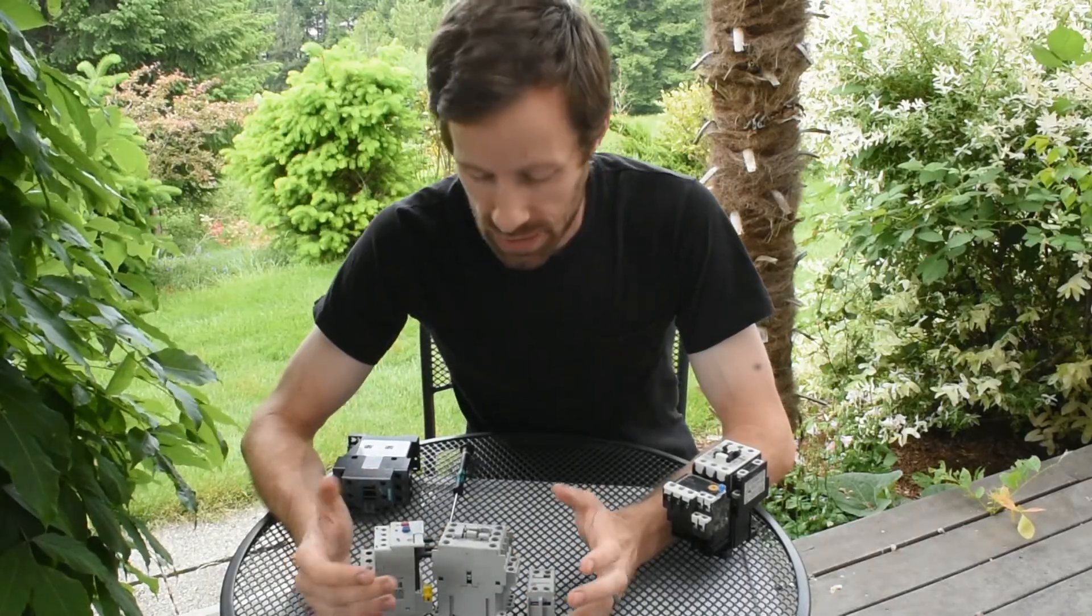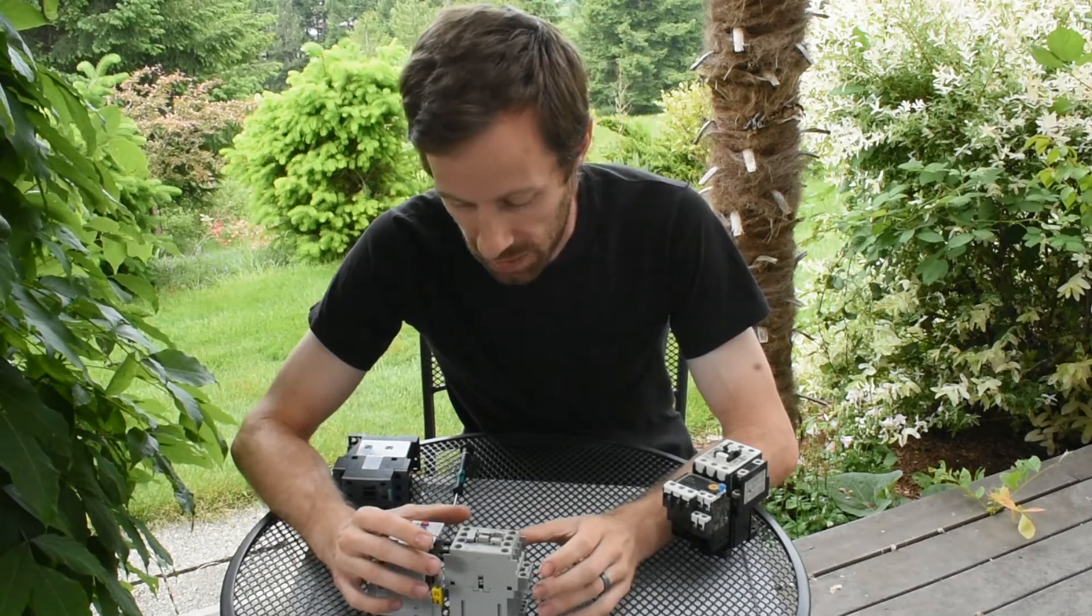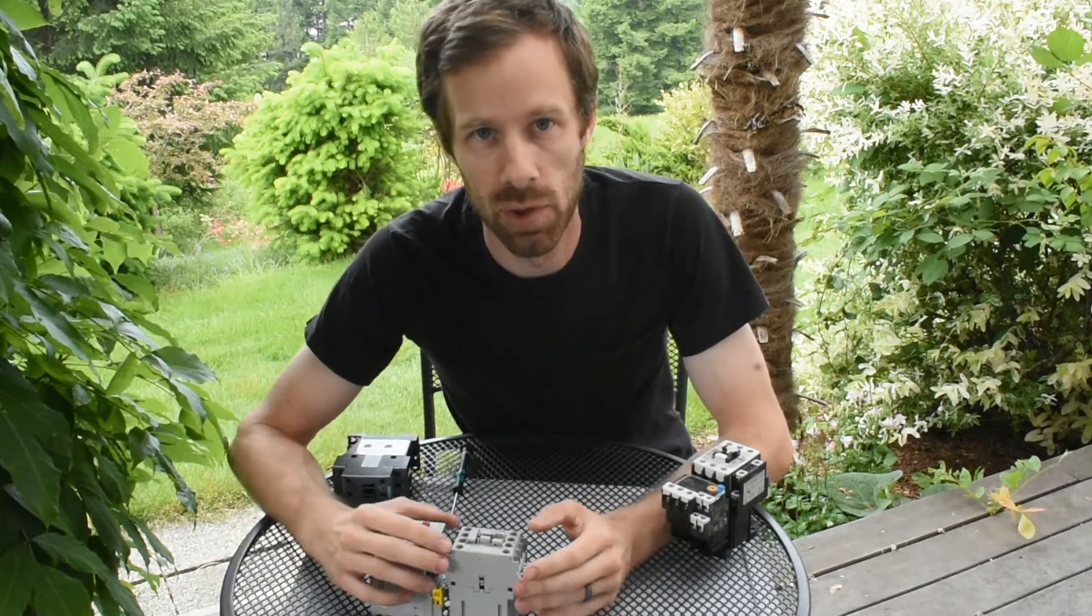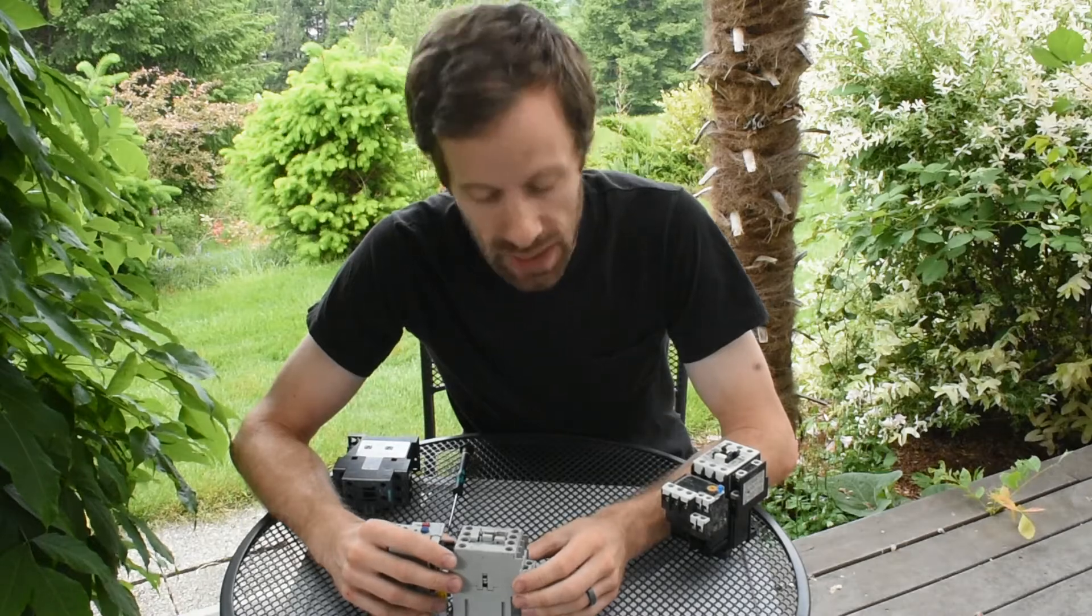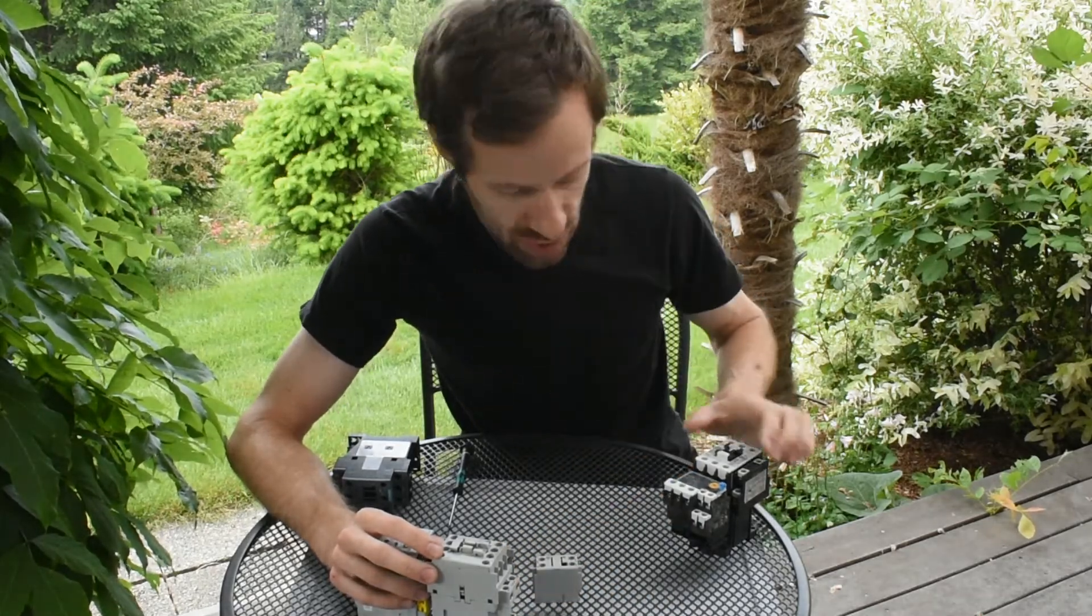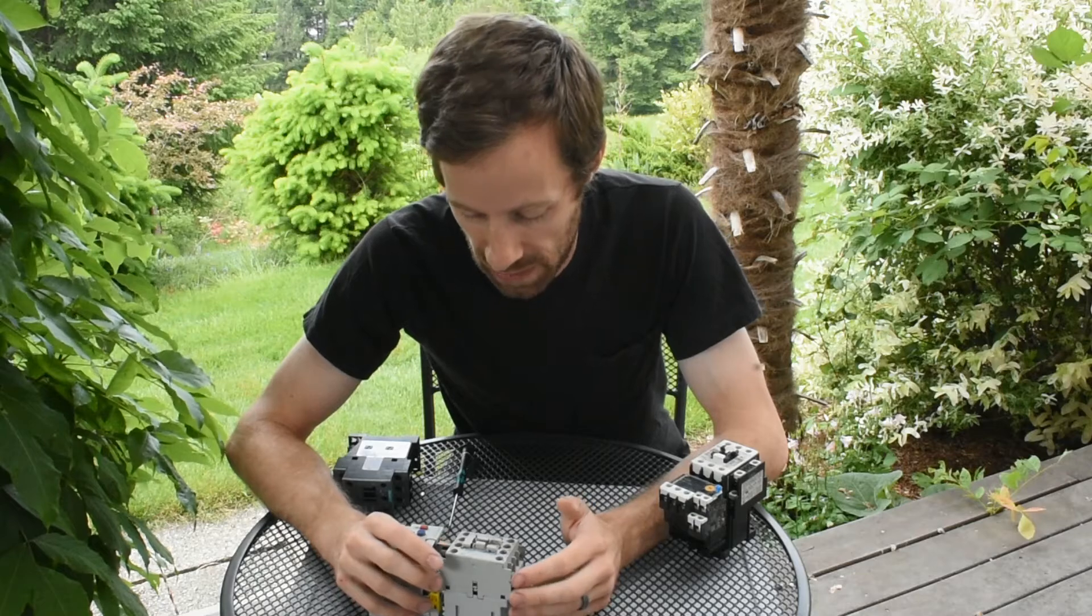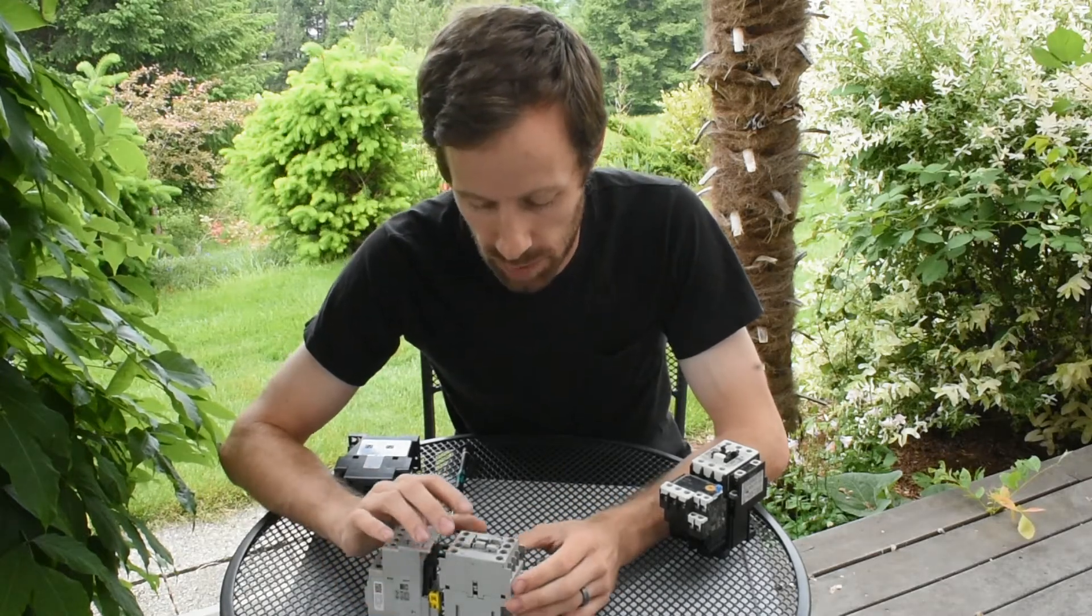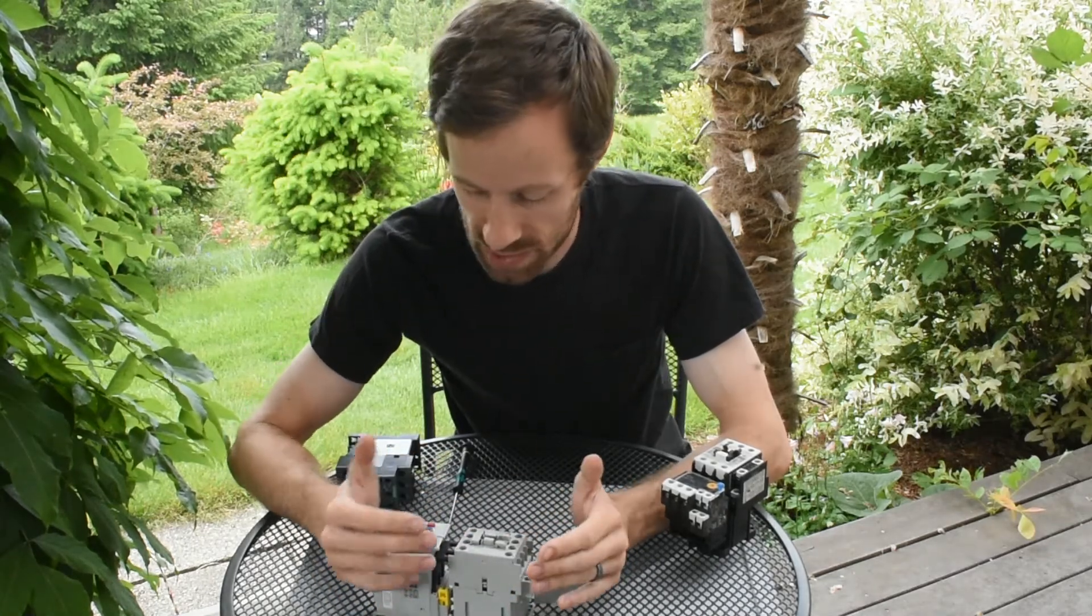So, there you can see all the components that are contained inside a typical motor starter. Now, some of the things that can usually go wrong with these starters are like I mentioned earlier with the diode inside. When it's charged with a DC voltage, then that voltage can build up and when you turn off the contactor, it throws that voltage back into the control device. Now, if that's something like a small relay or PLC module, that can be fatal to that PLC and you're going to have to be replacing those modules. So, that diode, which sometimes is inside it if it has the plus and minus marked, but often you'll just see it attached inside the set of terminals or inside a terminal block, you'll see a diode connected, which is used to prevent that voltage, which they call flyback voltage or freewheel voltage. Sometimes it's called a snubber diode. There's a lot of different names for it, but it's used to protect the circuit.